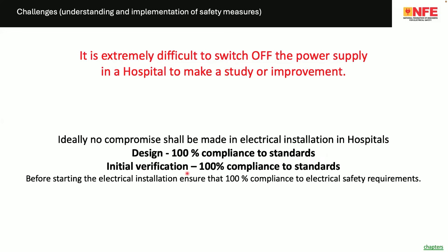Initial verification. The concept here is that before you start using electricity in an electrical installation, you are supposed to verify, meaning inspect and test the installation and rectify all the defects. Example, loose contacts. When you make a verification, with the continuity resistance test, you can identify all the loose contacts. You ensure that there is no loose contact. As a result, you get a highly reliable electrical installation. So before starting the electrical installation, ensure that 100% compliance with electrical safety requirements is met, because once you start, after that, you cannot really stop.